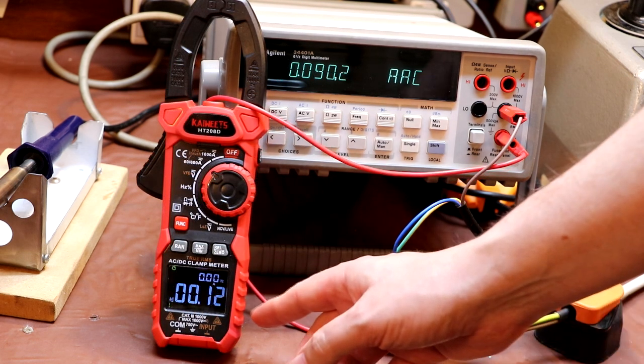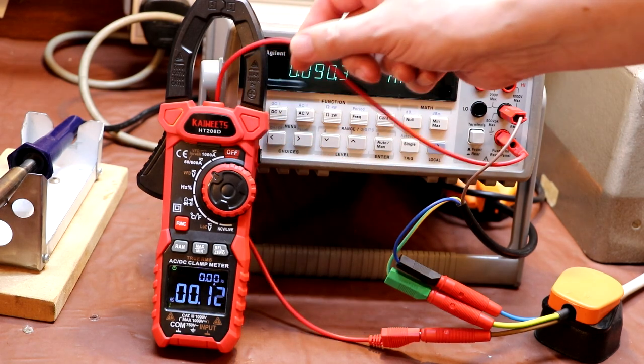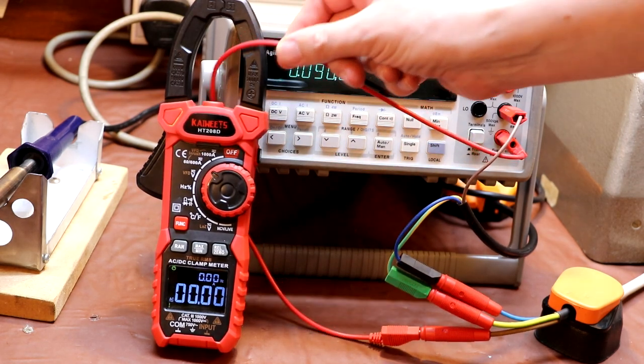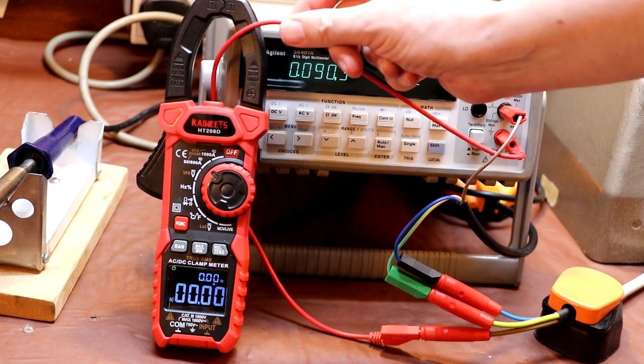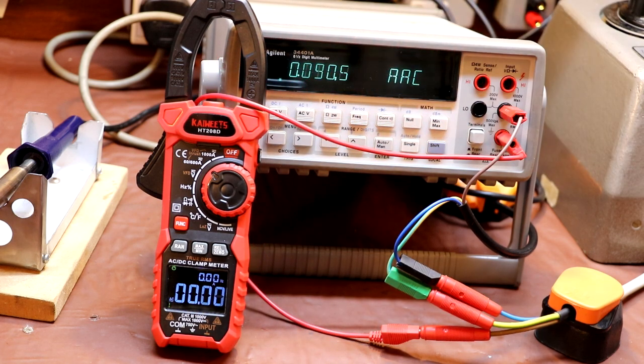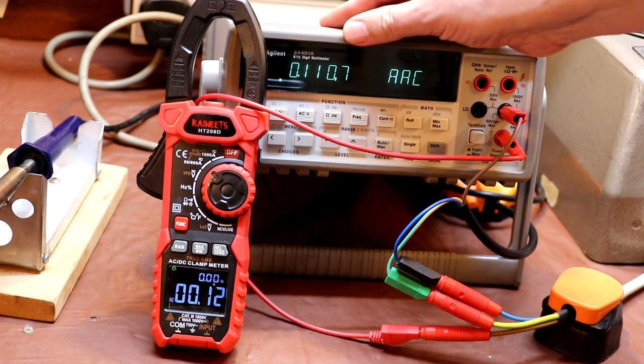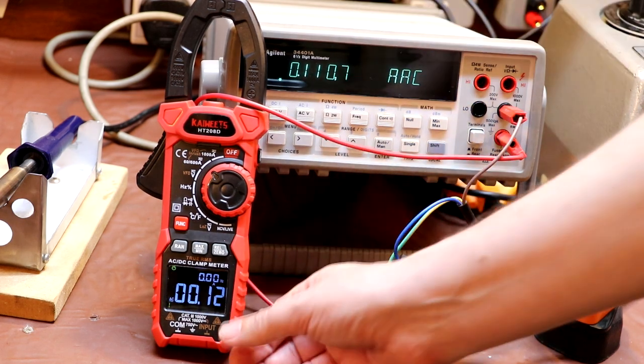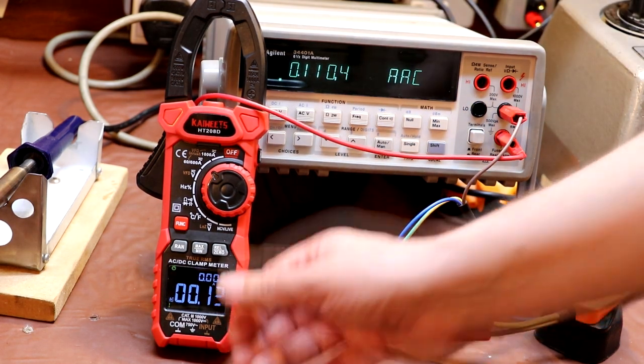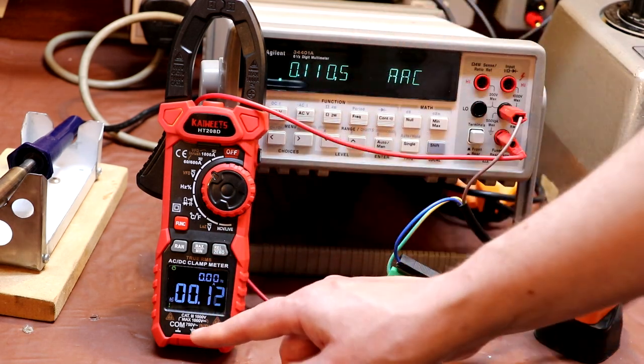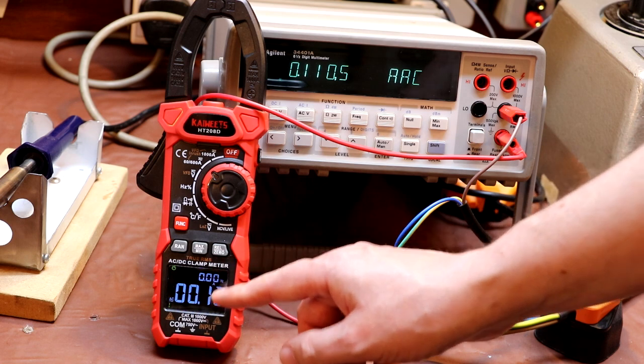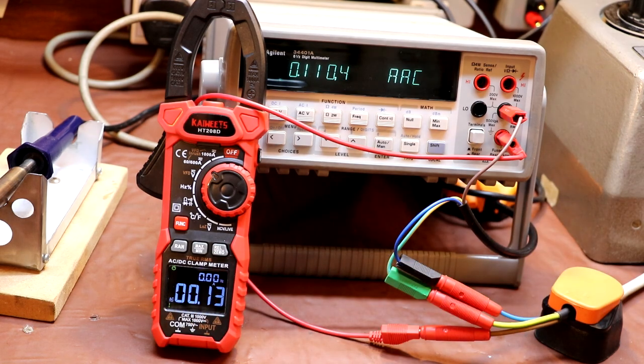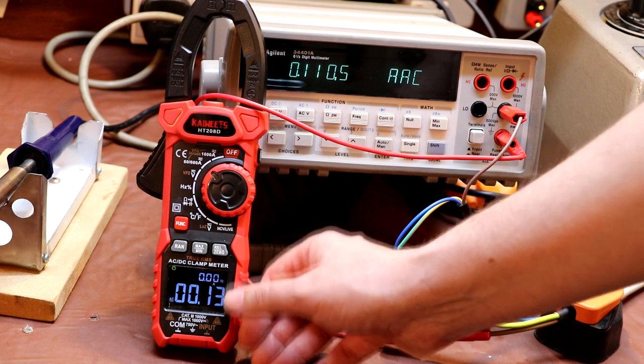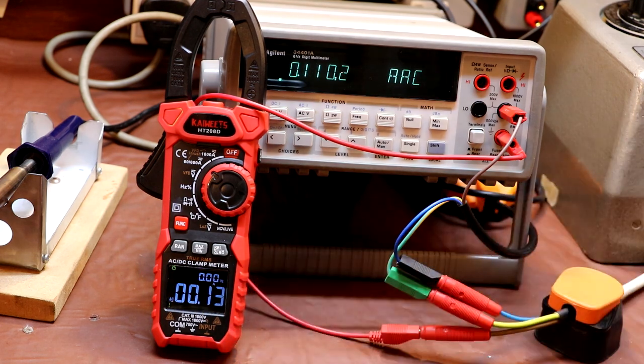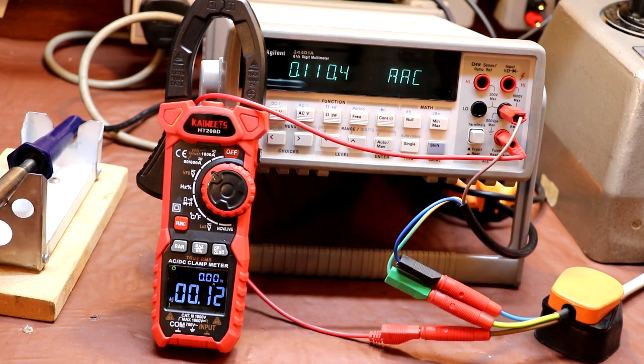90 milliamps now, and it is trying. I'm just wondering if the Y position is going to make any difference. Nope, doesn't seem to. Finally, with a set current of 110 milliamps, we're getting a consistent reading on the KAIWEETS. So we are within a few counts. We're within 5 counts of these meters, but it's a little bit disappointing that it doesn't actually start reading until we've got 100 milliamps. So this last decimal place of resolution is really not doing us very much good at the lower end of the scale.